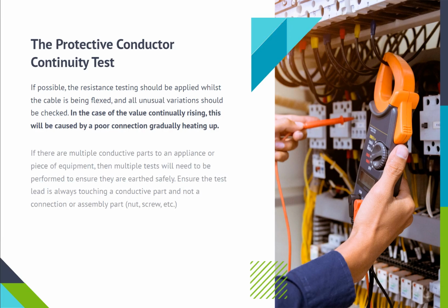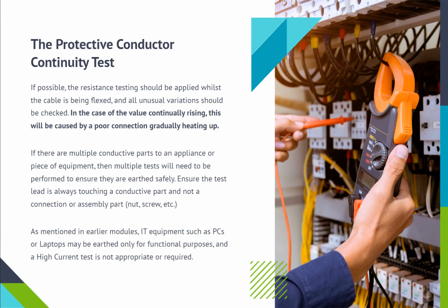If possible, the resistance testing should be applied whilst the cable is being flexed, and all unusual variations should be checked. If the value continually rises, this will be caused by a poor connection gradually heating up. If there are multiple conductive parts to an appliance or piece of equipment, then multiple tests will need to be performed to ensure they are earthed safely. Ensure the test lead is always touching a conductive part, and not a connection or assembly part, nut, screw, etc. As mentioned in earlier modules, IT equipment such as PCs or laptops may be earthed only for functional purposes, and a high current test is not appropriate or required.